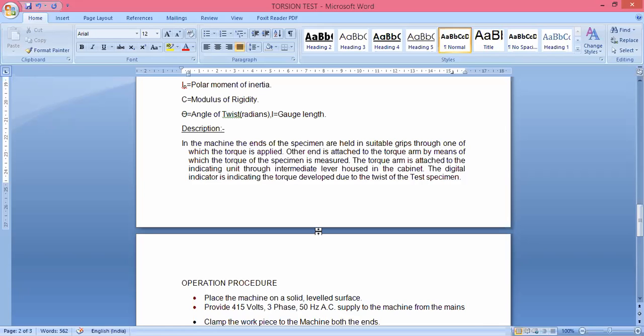So what we have here on the left side are the two vices for fixing the specimen. The right side vice is used for applying the torque, and the left side vice is attached to a torque arm by means of which the torque is measured. The torque arm is attached to the indicating unit through an intermediate lever housed in the cabinet. The digital indicator indicates the torque developed due to the twist of the test specimen.